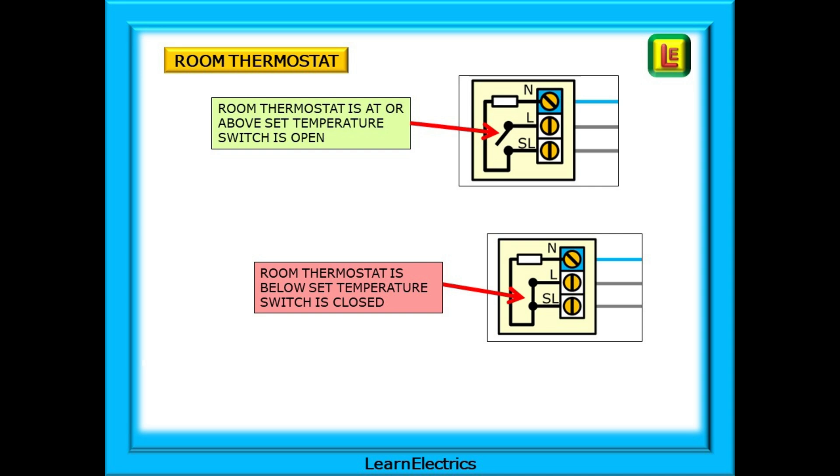The room thermostat is shown as a three terminal device. Of interest to us are the L and SL terminals. If the room or zone is up to temperature, then the switch will be open. L and SL will not be in the closed position. When the room temperature falls below the set temperature, or someone turns the thermostat up to a higher setting, the contacts will close. L and SL will be in the closed position allowing current to flow through the switch. Up to temperature, switch open. Below set temperature, switch closed.